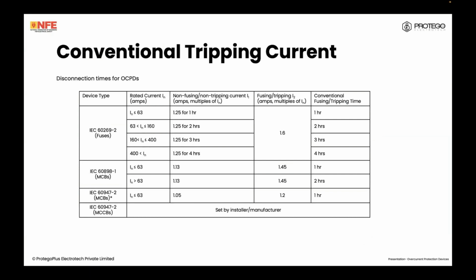Generally speaking, these will be given by the manufacturer for all devices, unless it is an adjustable MCCB, where depending on the overload release, the long time release, this is defined. But for say a fuse or an MCB, these are going to be defined. So for instance, for an HRC fuse, this is 1.6. Let's take a simple example, a 10 ampere HRC fuse to 60269 part 2: at 16 amps, it will trip in 1 hour. If it's a 10 ampere MCB to 60898 part 1, at 14.5 amps, it will trip in 1 hour. These are talking about what currents the protected device will disconnect at in overload conditions.